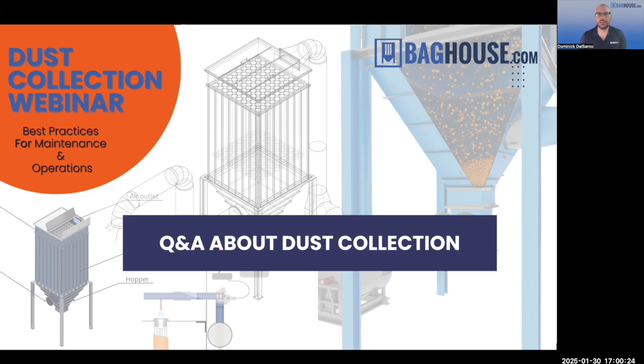What are some common things we see with the airlocks, the hoppers, and all of that kind of stuff that cause problems? So hopper flow problems are really common, and we can always spot them because you go out on site and you look at the hopper and it's all banged up. You can see where they've taken a rubber mallet or a hammer and banged on the side. Okay, there's a discharge issue that they're dealing with.